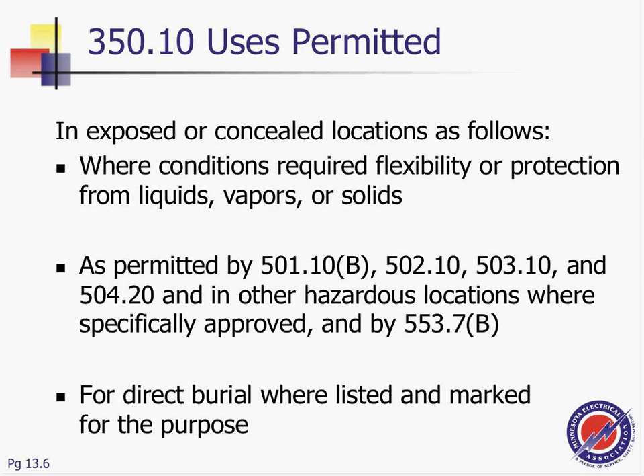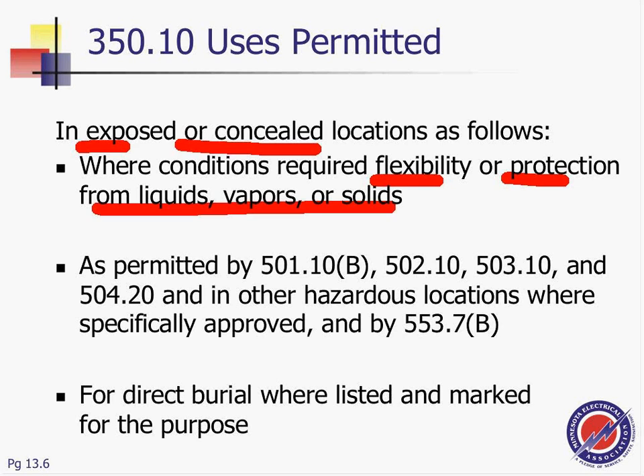Use is permitted. Moving on, like any other conduits, where can we use it? Exposed or concealed, bring it on, no problem. As follows: where conditions require flexibility, or protection from liquid, vapor, or solids. So that's basically it, really. You can use it exposed or concealed, like in slabs, but what makes you use it is protection from liquids, vapors, or solids, mainly liquids in the application.